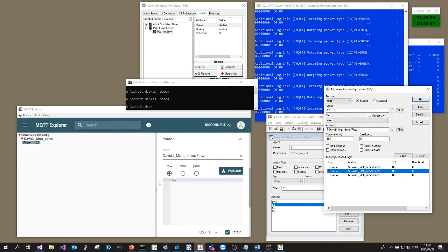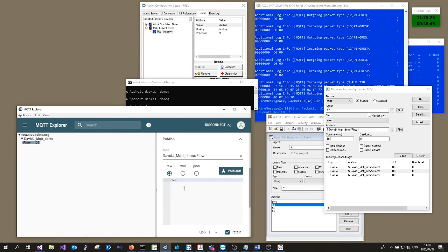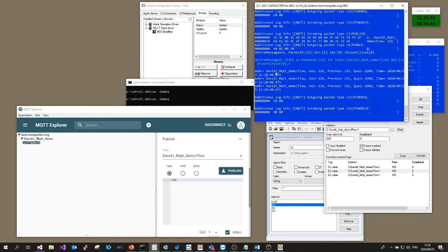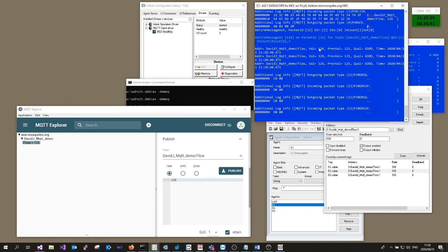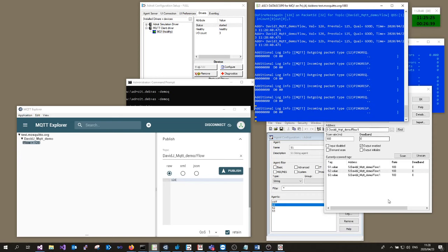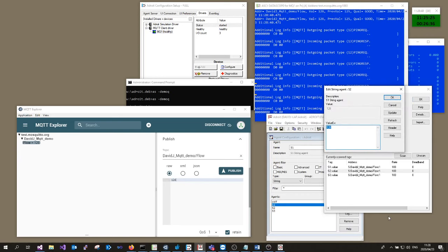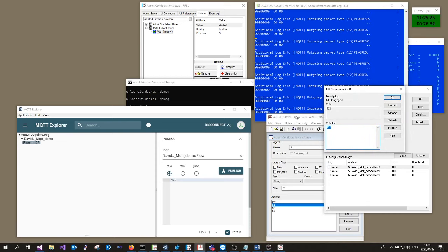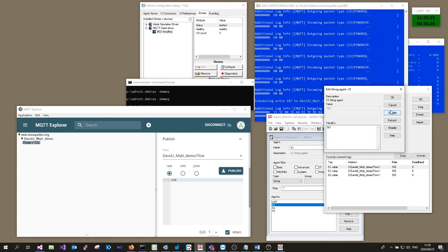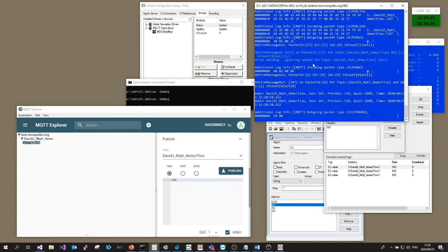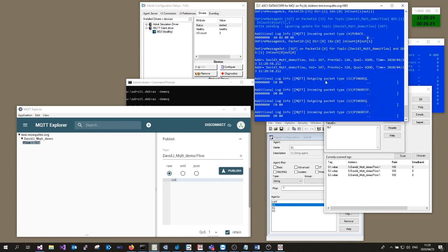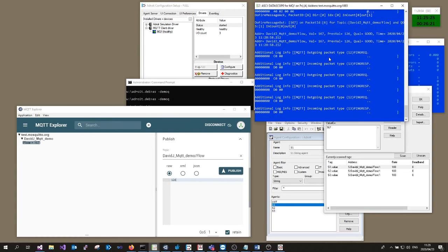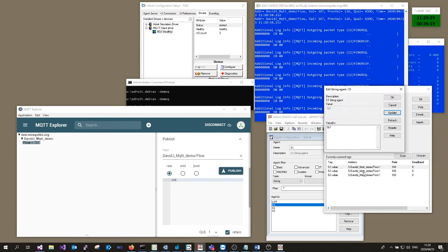All right, so basically I'm again in the little block, and I'm going to make the block publish 126. You can actually see in the data scope a message came in, and the 3 connected items got 126. What's nice now is I can write down 167 back from the SCADA in the other direction, and you'll see it go out, and you'll see it reflects back to the other items, 167. So very nice mechanism.